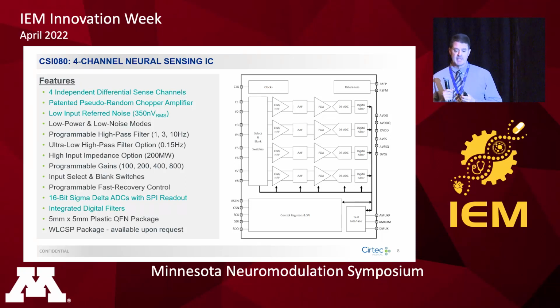We come into this low-noise amplifier/high-pass filter combo, which is that chopper amp, into a programmable anti-aliasing filter, then a programmable gain array to cover a wide range of signal sizes. Then we go into a delta-sigma A-to-D converter and do the first round of digital filtering on chip. The output is a digital word representing every sample at the input—basically 4 known good digital words. Down at the bottom there's overhead: control registers to program all the variable filters and variable gain, all programmable via SPI.